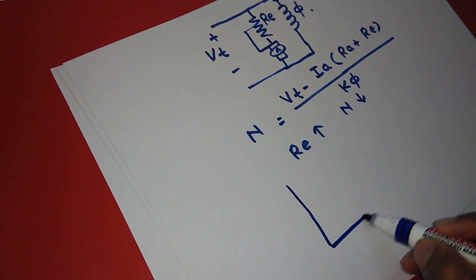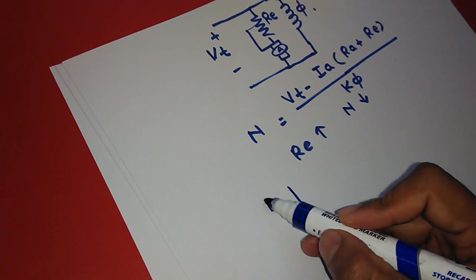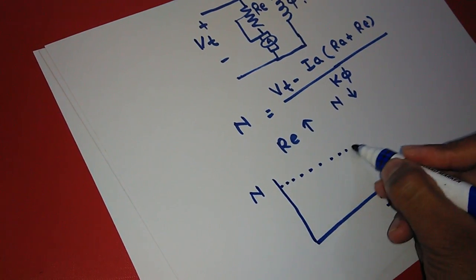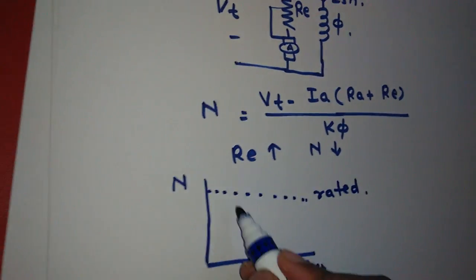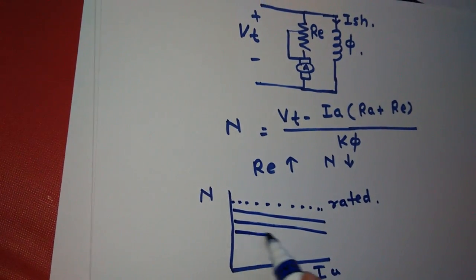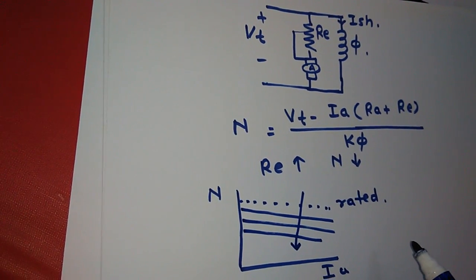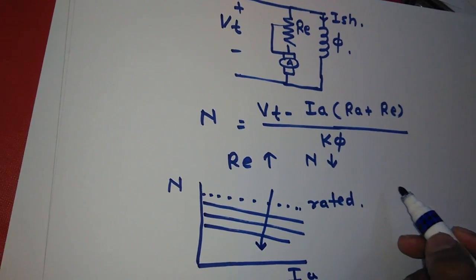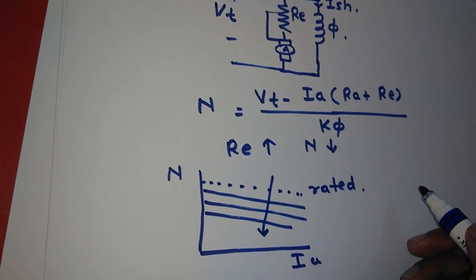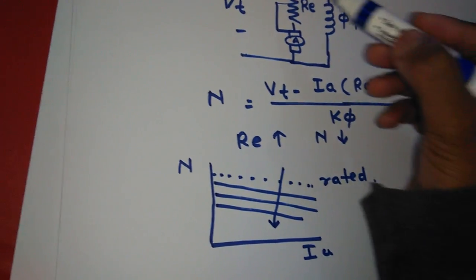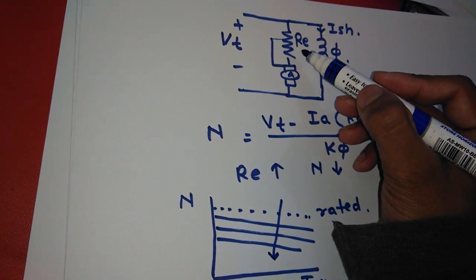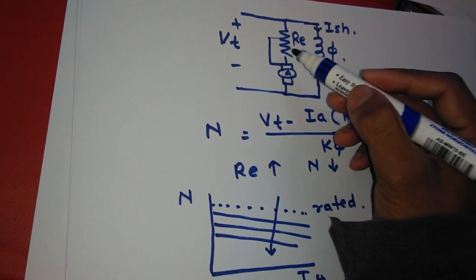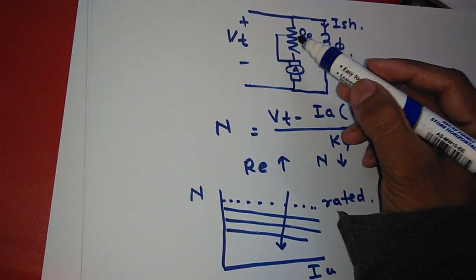If we see the characteristic of speed versus current, we can see that this is the rated speed and speed control is achieved below the rated speed. By this method we can change the speed below the rated speed. It has some problems, which is why it is not used widely. The problem is that whatever external resistance is connected, it causes power loss, so there is too much power loss in the armature connection.